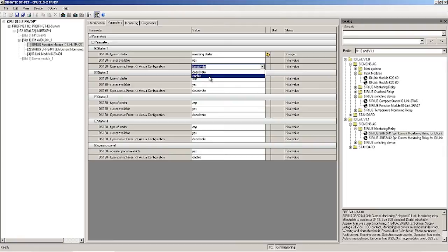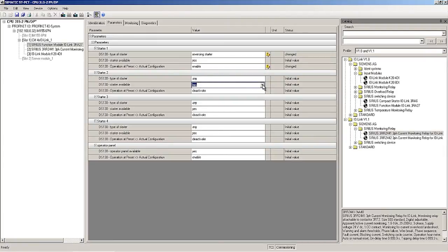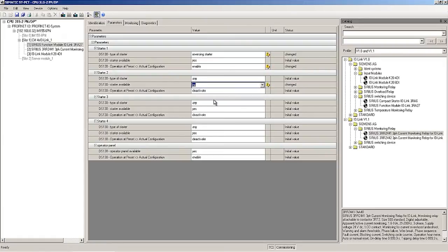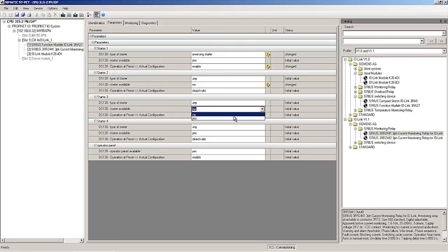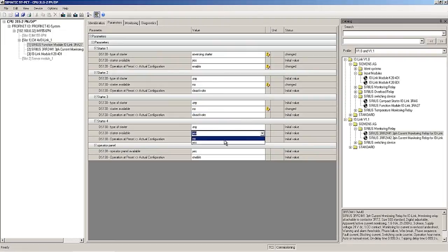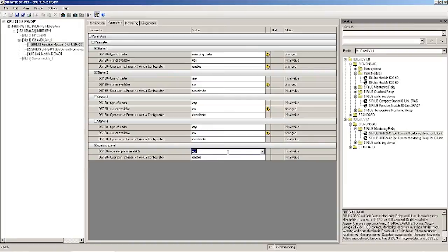Various function modules are available for the different starter types, but always with the same reversing starter and device IDs. Because up to 4 starters can be grouped on an IO-Link master port, the parameters for starters 2 to 4 are visible in the PCT tool. They are set to unavailable. Because we do not have an operator block, no is selected.